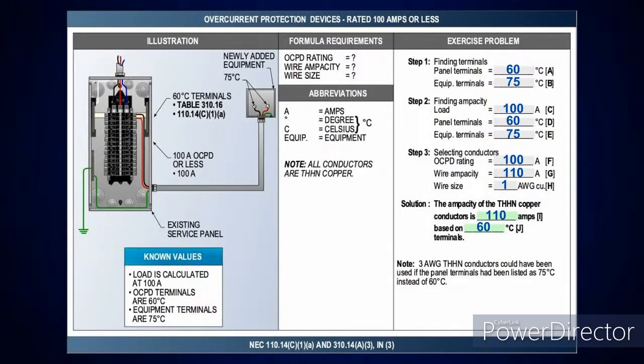All right. So last week we were going over the terminals, and I explained how we go about sizing these terminals. Right here, I've got 60 degree C terminals at the panel, but I have 75 C at the newly added equipment. Naturally, you're going to base this ampacity on what? The 60 degree C terminals, okay? Now, if I put a breaker there that was, say, 60/75, then naturally I could go to the 75 degree C terminals, okay? But this was one that was just put together for everybody to follow.